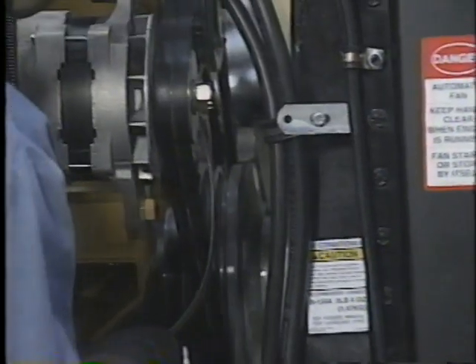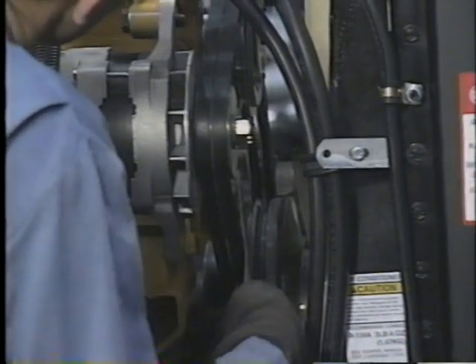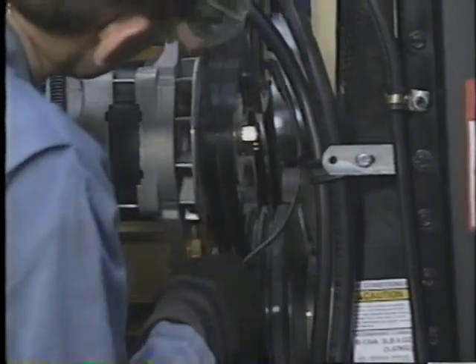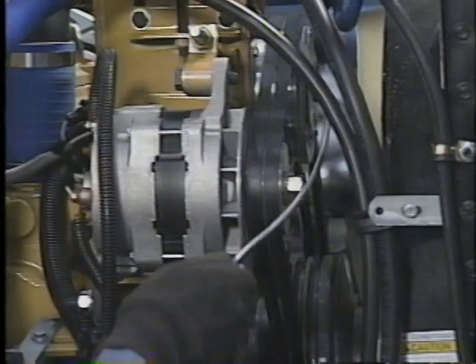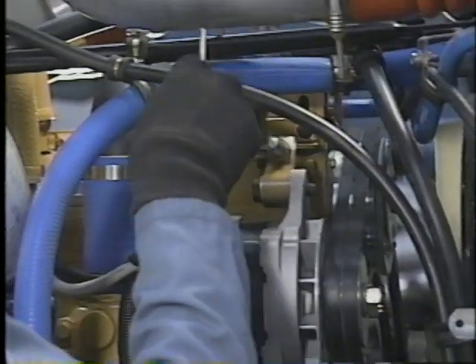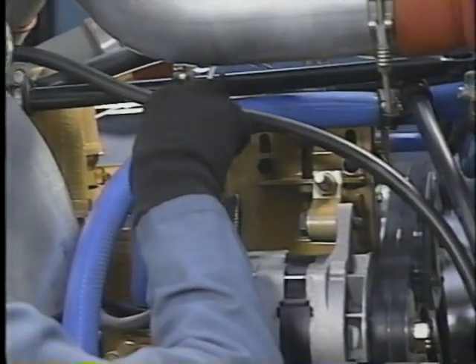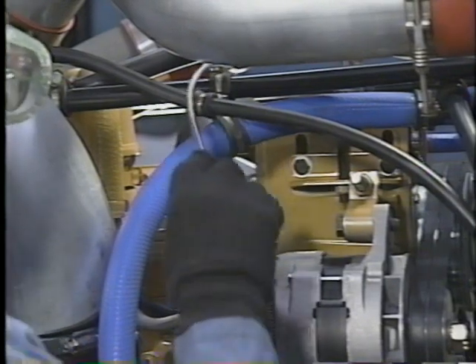Whenever pressure is low on both sides of the system, or pressure is normal but the AC isn't putting out sufficient cooling, or the gauge readings indicate the presence of air and moisture in the system, you must check for leaks along all lines and fittings. Several methods are available, but Freightliner recommends use of an electronic detector for fluorine, which produces an audible warning when a leak has been discovered. Pressurizing the system with dry nitrogen helps to find slow leaks.